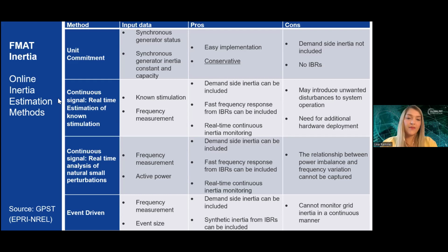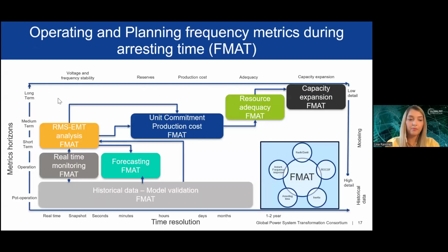Other approaches, such as event-driven ones, help to understand if the other methods are working well. But that is not continuous inertia monitoring. It is only when we have events in the system that we can track demand side inertia and also inertia from IBRs. But the problem is that it's only under events, so it's not continuous tracking of inertia. It's only when we have an event in the system.